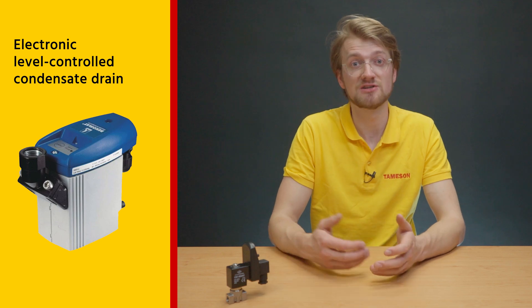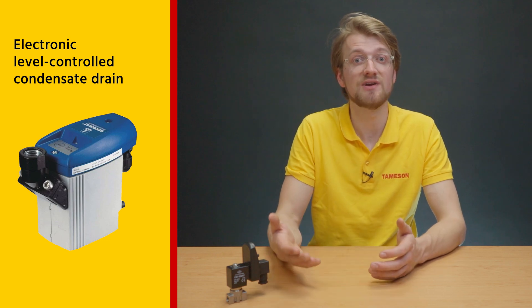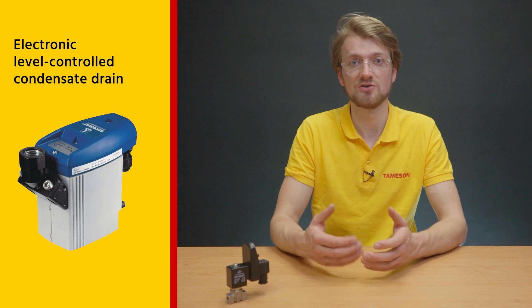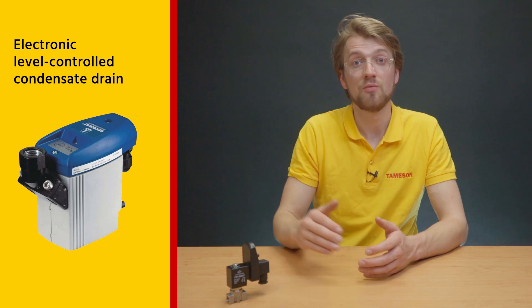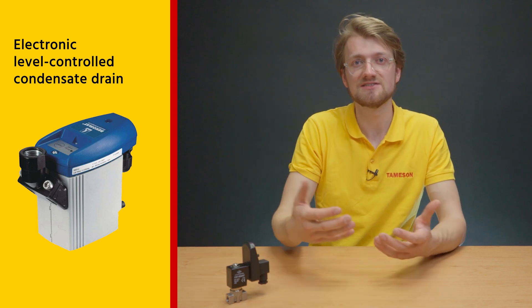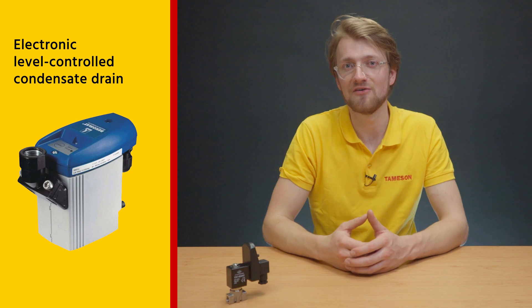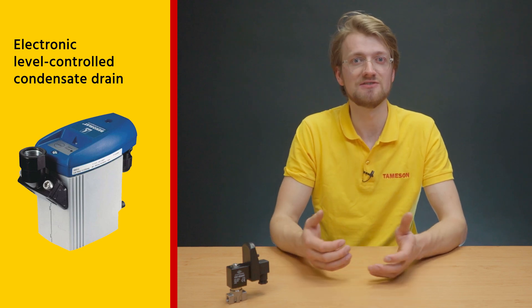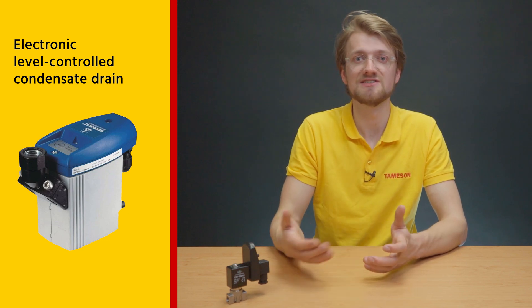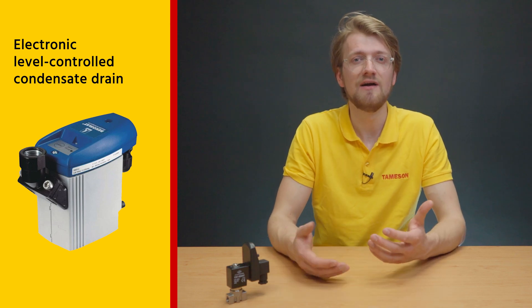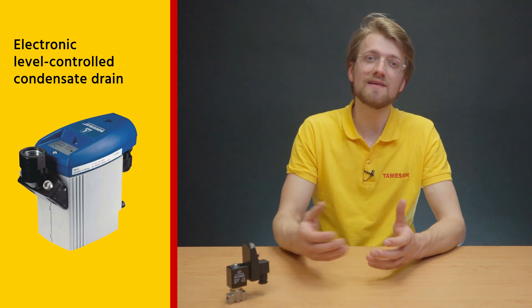Second, an electronic level controlled condensate drain. They have an electronic sensor that monitors the condensate level. When it hits an upper limit, it opens and lets the condensate out through the solenoid valve. When the level goes back down, it senses this and closes the valve until the condensate level rises again. Therefore, there's no loss of compressed air. However, they tend to be more expensive than other options.